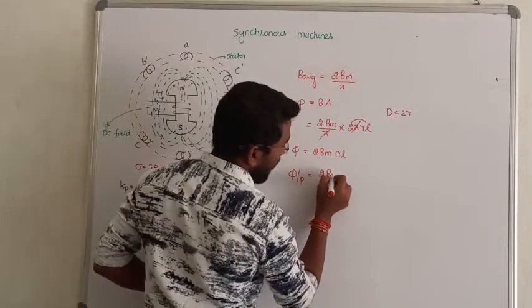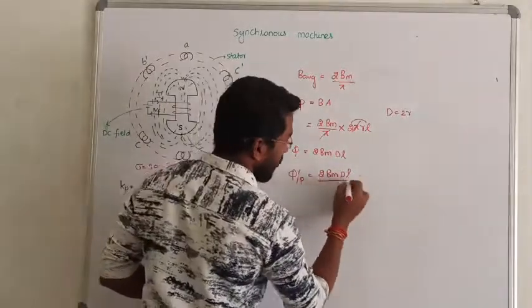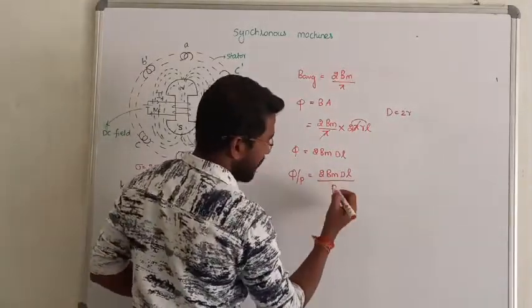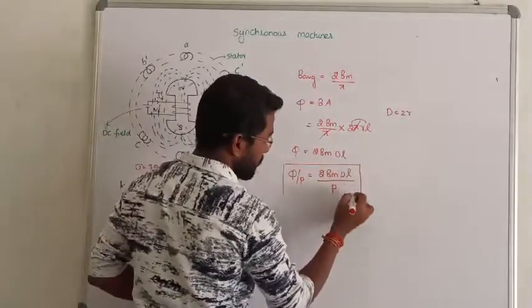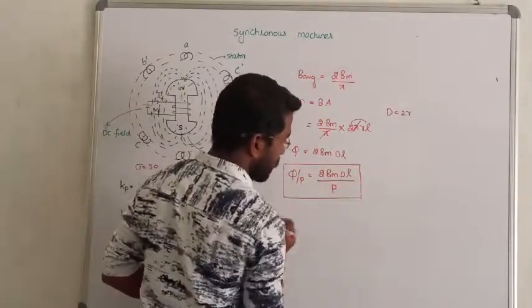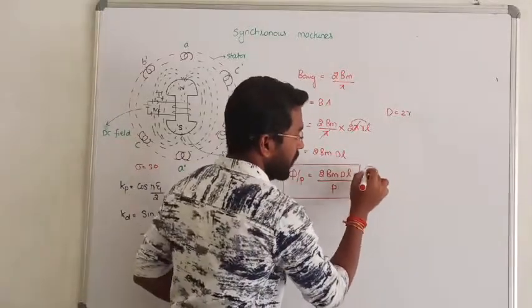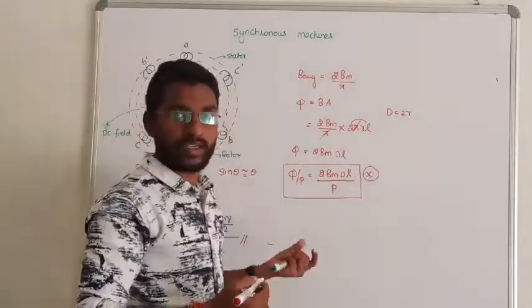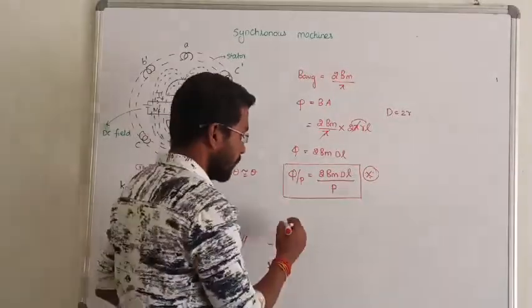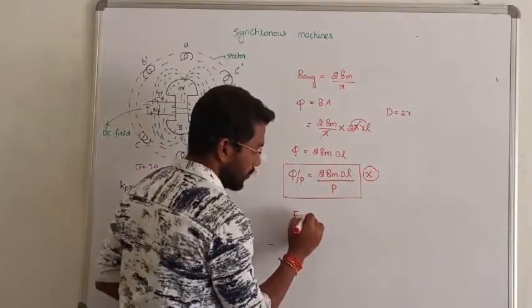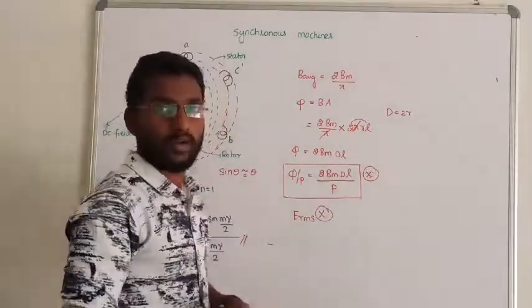Now you can calculate flux per pole - maximum flux per pole. That's 2 times maximum flux density times diameter D times axial length divided by the number of poles P. That's how we calculate the maximum flux generated per pole in synchronous machines.